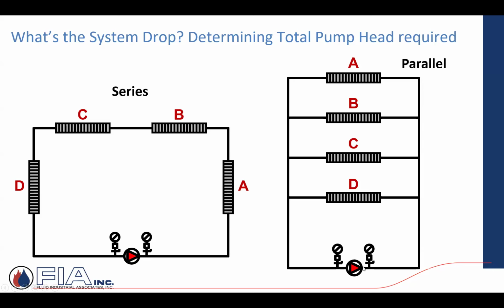Over here, now I'm in parallel. This is different. As this pump is pumping the total desired needed flow rate, I don't have to add up the pressure drop of every branch here. Why? Because as long as I calculate the pressure drop of the branch with the greatest pressure drop, then I have enough pressure differential head capacity from the pump to overcome the lesser pressure drop loops. So all things being equal, this radiation is all the same, the required flow rates are the same. This just happens to have the longest run, so the most amount of piping associated with it. So I'd want to calculate that to establish my required pressure drop.